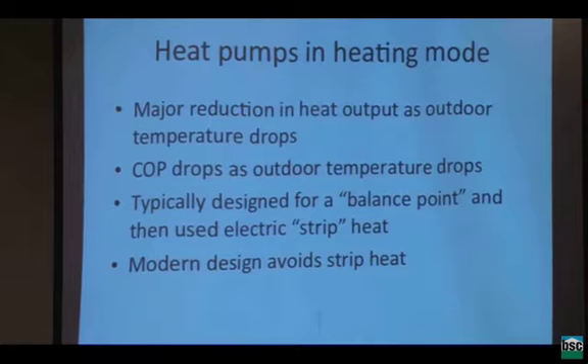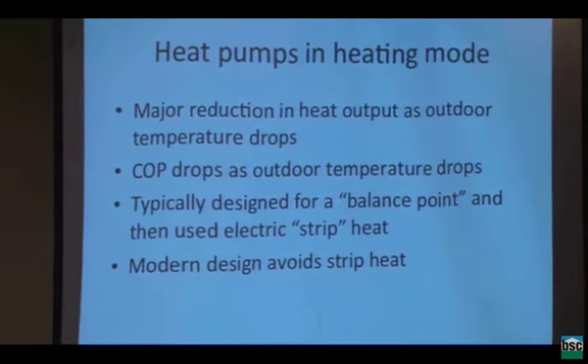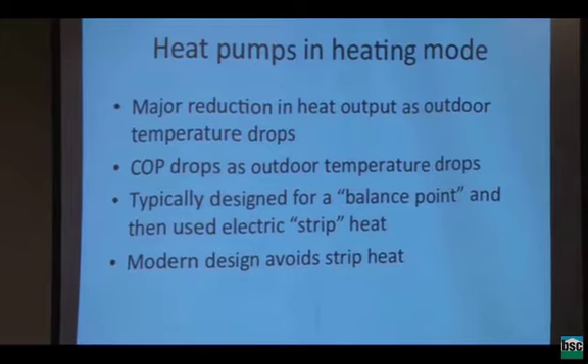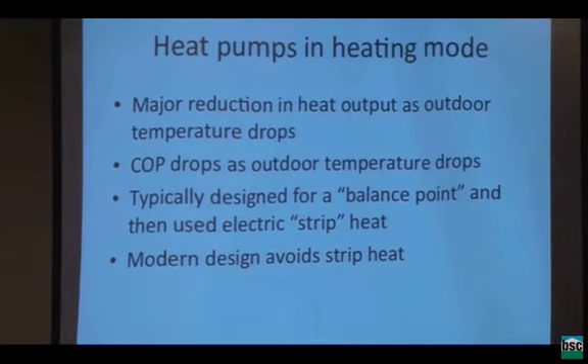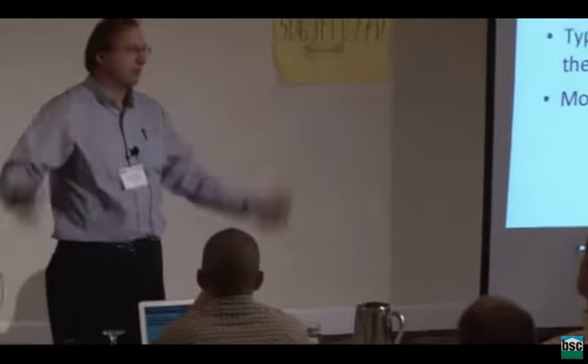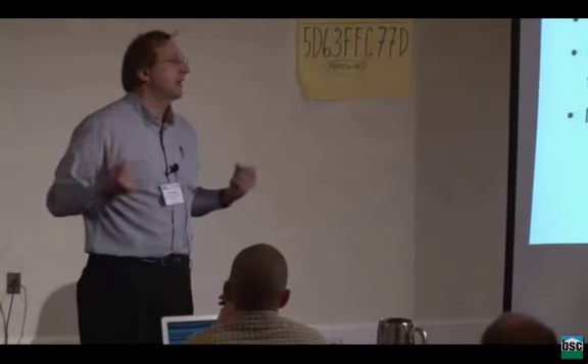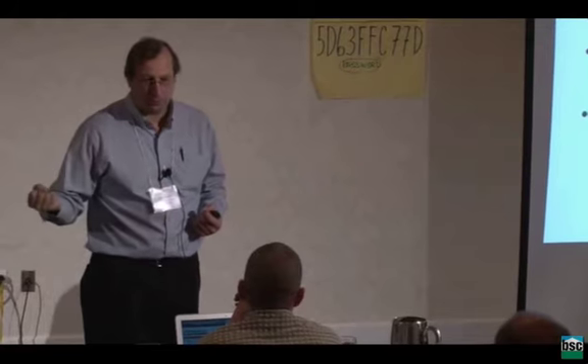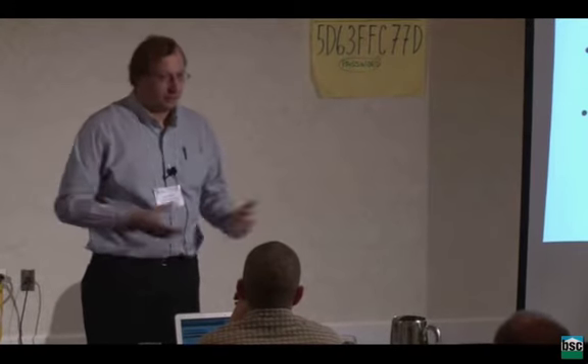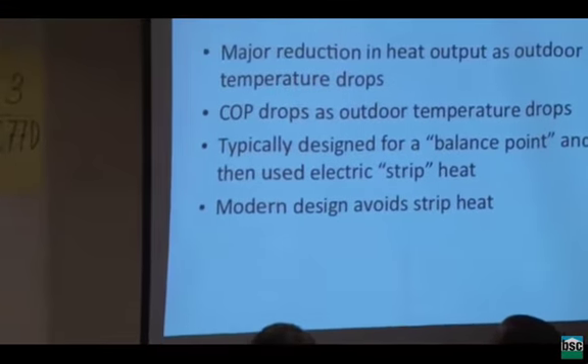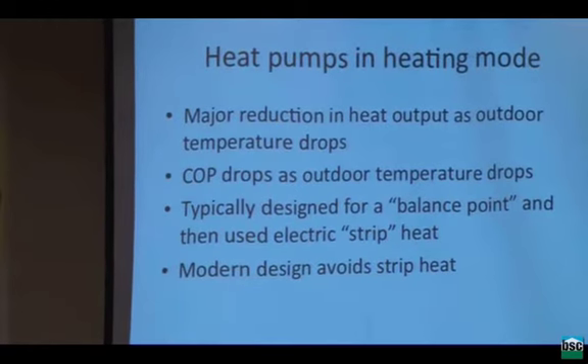So in the good old days, we started heat pumps the first time around in the 70s in any sort of serious way. The heat pumps were basically accepted that you weren't going to be able to heat the house when the air temperature was below about 35 or 40 degrees, right? They just said, look, we're just not going to be able to get enough capacity for the crappy houses we're building that needed 50,000 BTUs an hour with the technology they had at an outdoor temperature of 40 degrees. So they would supplement the heating with electric strip heat, right? Everyone knows that. And so when the temperature dropped below X, what they call the balance point when you're in the heat pump business, the electric strip heat would kick in.